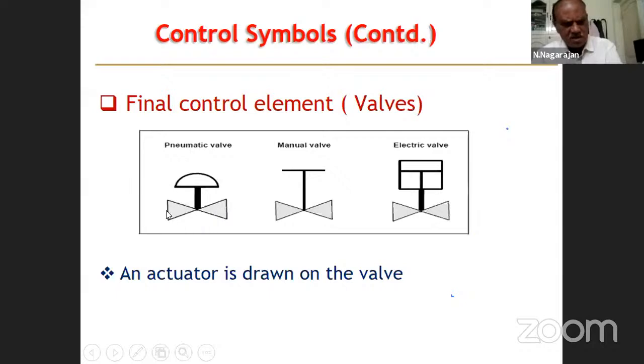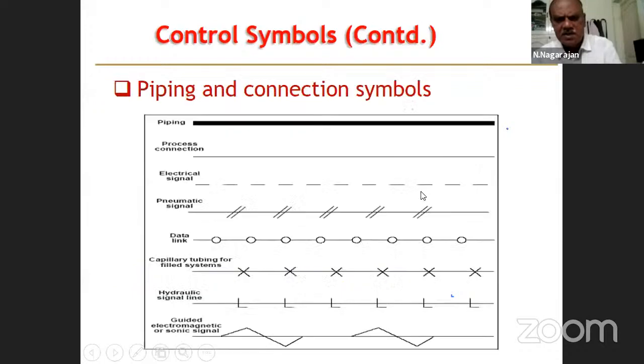Most of the automatic control valves are this type. Manual valve is where manually you have to go and control, open or close. Electric valve means a motor will be attached. Large size valves cannot be opened by pneumatic air, definitely not by human beings. So in such cases, you will have a motor. These are called motor operated valves, so electric valve. These are called actuators. This is the valve. The symbol above is the actuator. It shows whether it is pneumatic or manual or electrically operated.